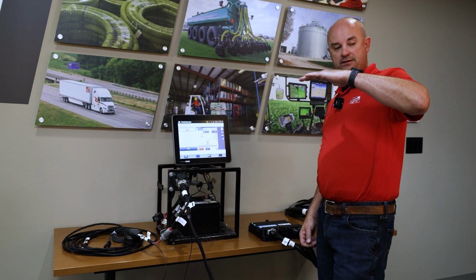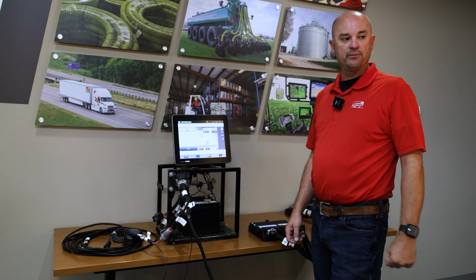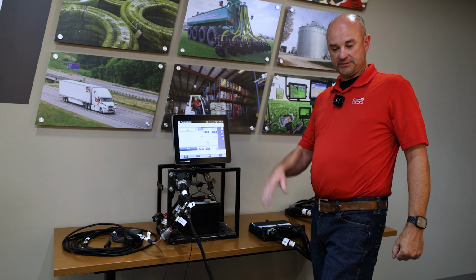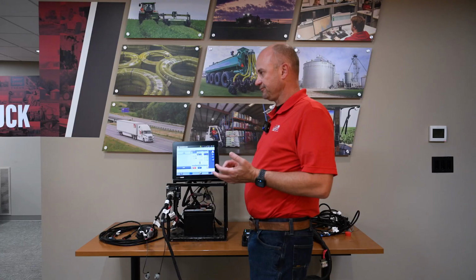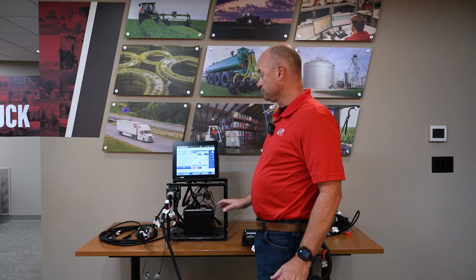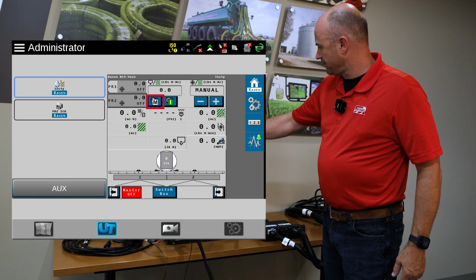If it stays steady when you do that, that tells us you probably have a control valve or a wiring issue. If it stays crazy the whole time, then we probably either have a flow meter or a strainer issue, or cooler issue as far as that goes. Flip it back into automatic.